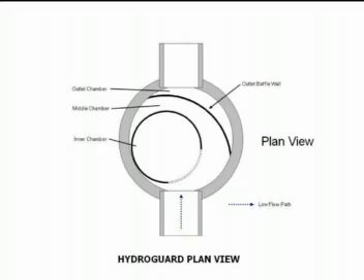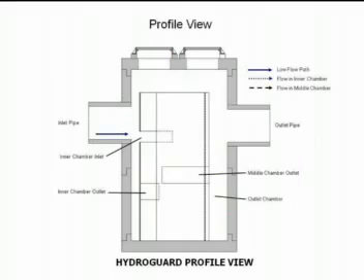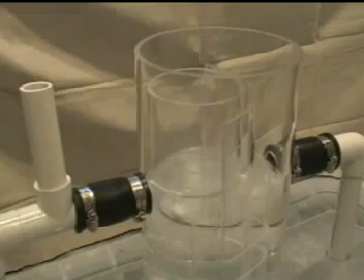HydroGuard has both a low flow path and a high flow path. Low flows enter an offset cylinder called the inner chamber. The inner chamber has an inlet opening facing the inlet pipe. There is a submerged outlet opening in the inner chamber along the concrete wall facing the inlet pipe. The opening into the inner chamber is restricted so that high flows bypass the inner chamber. Both low flows and high flows must flow through an outlet baffle wall, such that even high flows receive partial treatment for floatables and large solids.